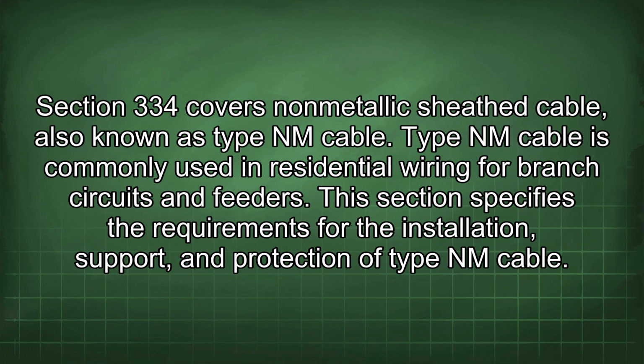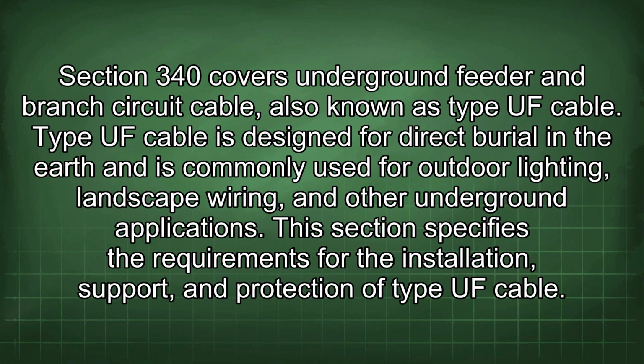Section 334 covers non-metallic sheath cable, also known as Type NM cable. Type NM cable is commonly used in residential wiring for branch circuits and feeders. This section specifies the requirements for the installation, support, and protection of Type NM cable. Section 340 covers underground feeder and branch circuit cable, also known as Type UF cable. Type UF cable is designed for direct burial in the earth and is commonly used for outdoor lighting, landscape wiring, and other underground applications. This section specifies the requirements for the installation, support, and protection of Type UF cable.